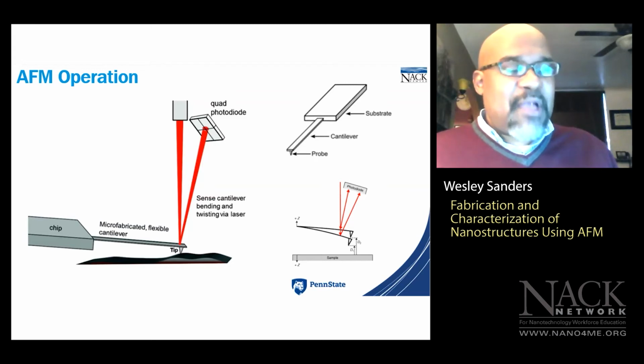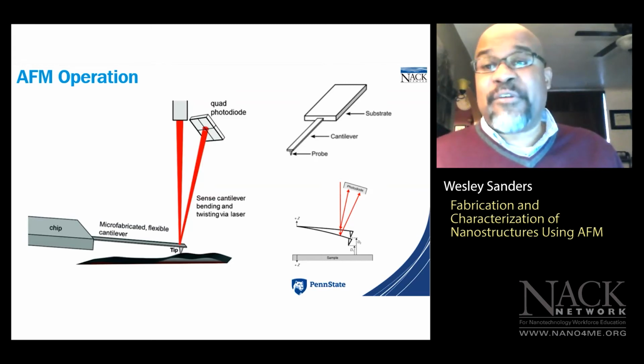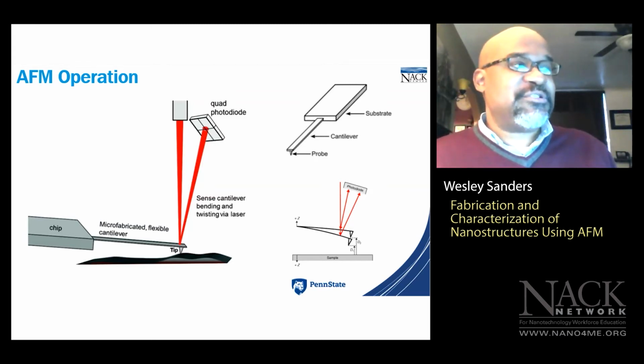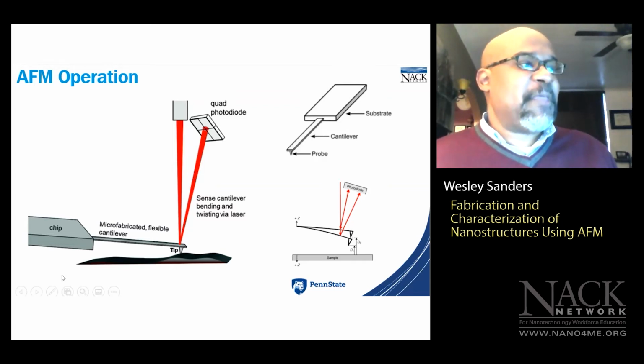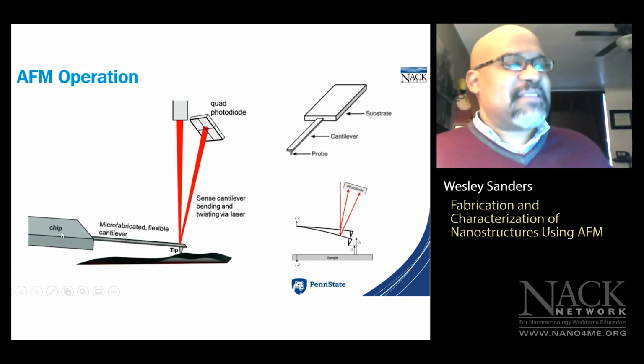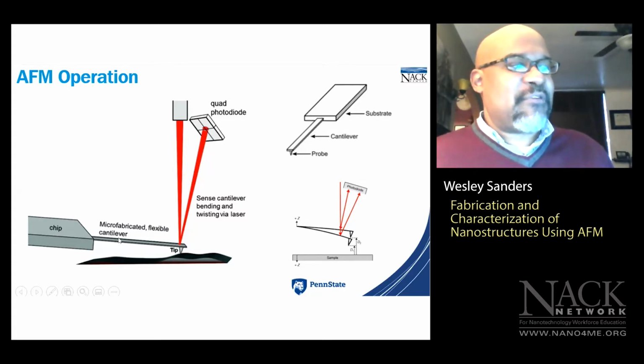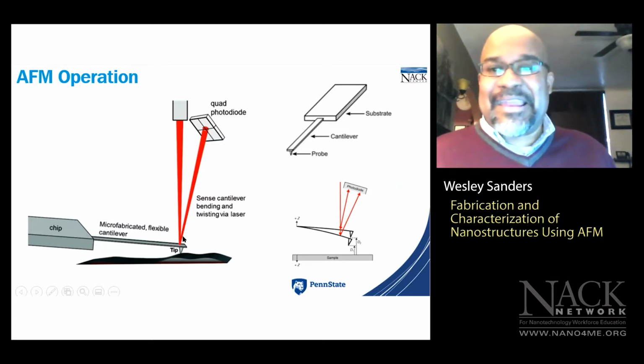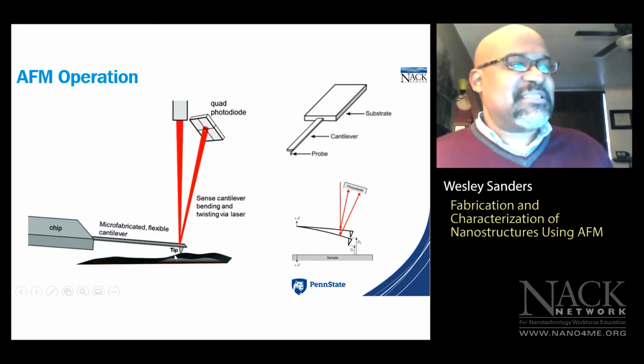So the AFM's primary role is to record surface topography. And in order to do so, there are some key components that the AFM uses. So we have our probe, which is an inclusive term that involves the chip. That's how we mount the probe into the AFM scanner.